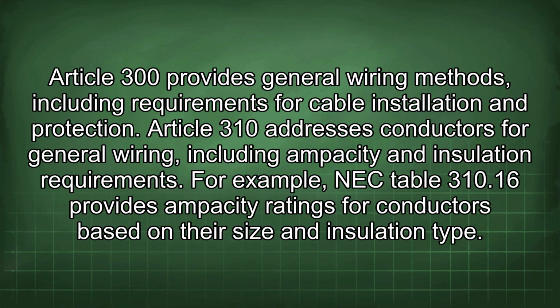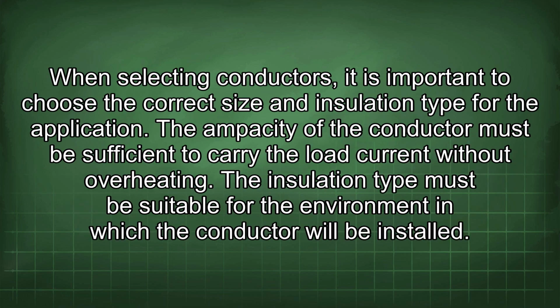Article 300 provides general wiring methods, including requirements for cable installation and protection. Article 310 addresses conductors for general wiring, including ampacity and insulation requirements. For example, NEC Table 310.16 provides ampacity ratings for conductors based on their size and insulation type. When selecting conductors, it is important to choose the correct size and insulation type for the application. The ampacity of the conductor must be sufficient to carry the load current without overheating. The insulation type must be suitable for the environment in which the conductor will be installed.